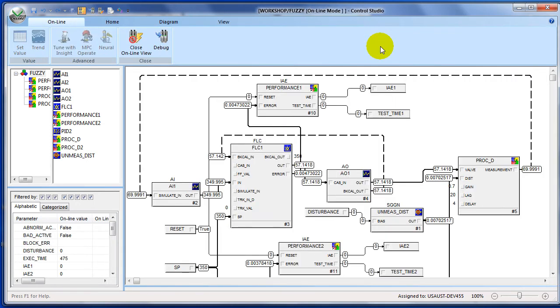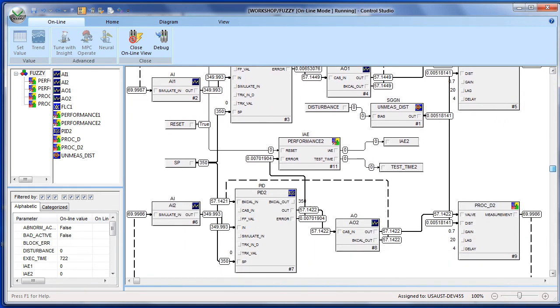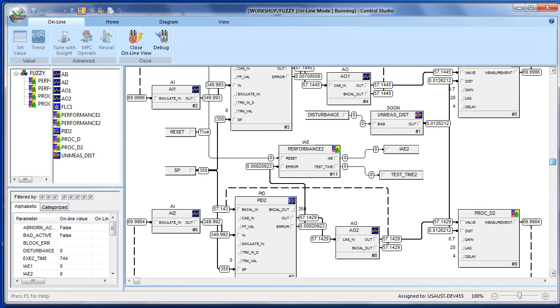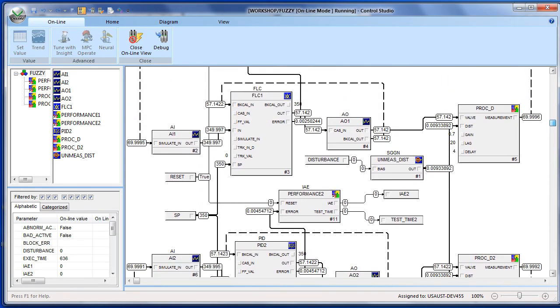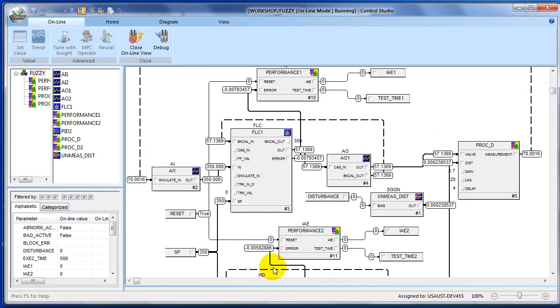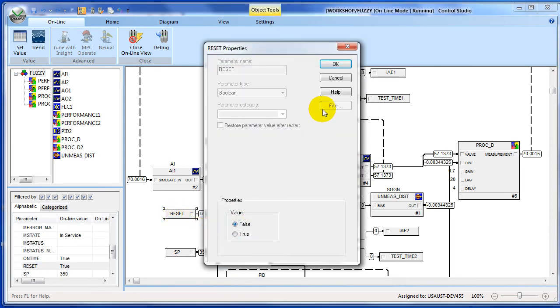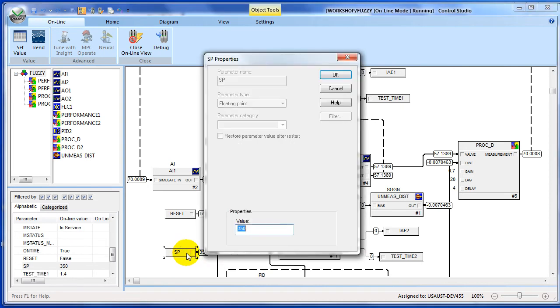So let's look at our control online where it's running in the controller. In this particular case, the reset is set to true, so our performance index is being set to zero — we'll start out at a value of zero. We notice that the fuzzy logic control is right on set point of 350°F, as well as the PID control is right at set point of 350°F. To demonstrate the performance difference, we'll set our reset back to false, which means our integral of absolute error will now be calculated, and we'll change the set point from 350°F to 400°F.